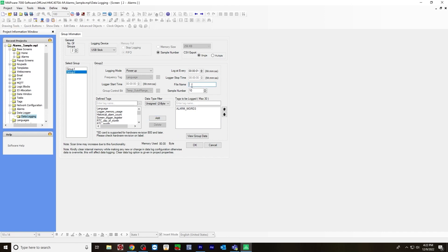File name can be whatever you want. I'll name it log test. Sample number will have to be anything 10 or more. You can change this to 15 or whatever you like. At this point you can hit OK. When the alarm goes off, it'll log onto the USB stick as a CSV file that you can view later on.